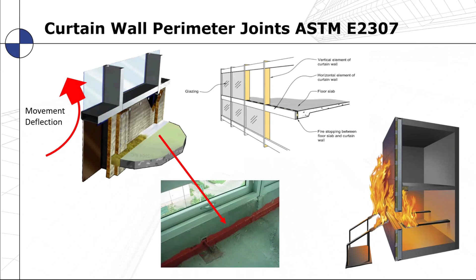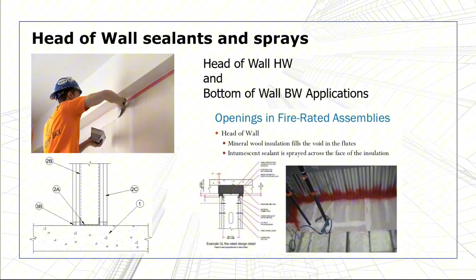Head of walls use sealants and sprays quite often. Head of wall joints are where the gypsum moves up to a concrete deck above. So that picture on the top left or the picture on the bottom right, that's where a movement joint is allowed to allow the floor up above to compress up and down on the gypsum and keeps it from cracking and things of that nature. But the most common method used in fire stopping these is some type of mineral wool backing material placed inside the cavity, and then it's sprayed over with a red or white or different color Firestop materials.